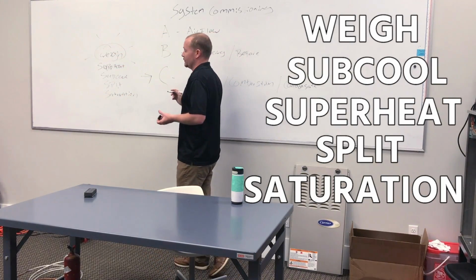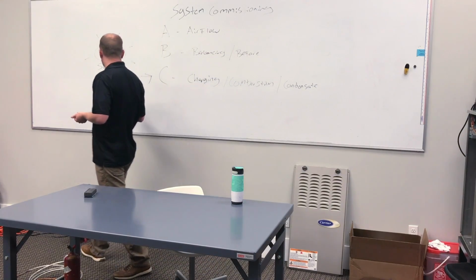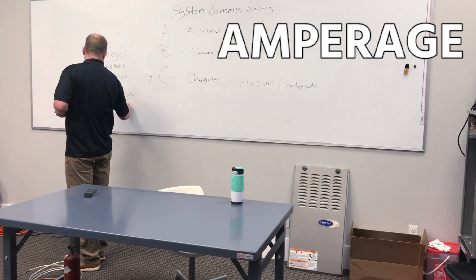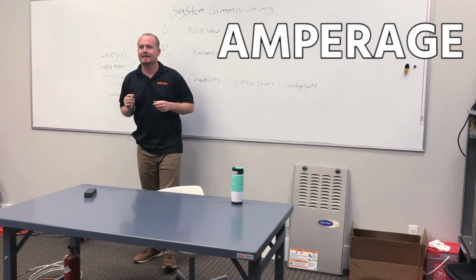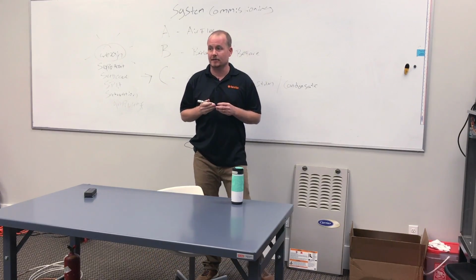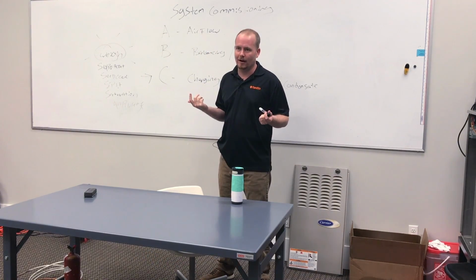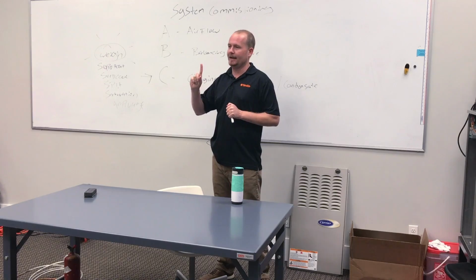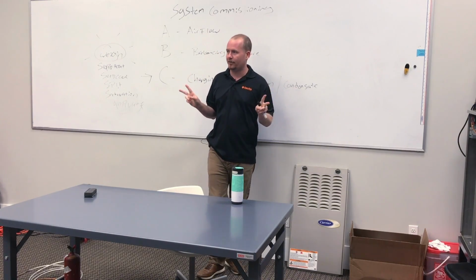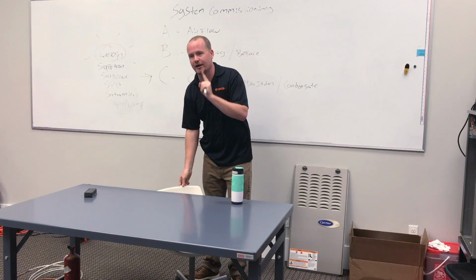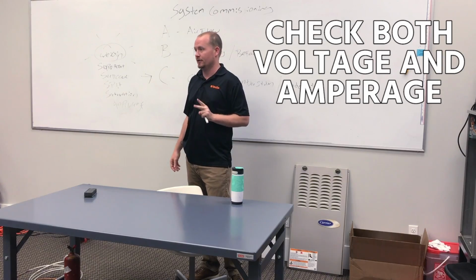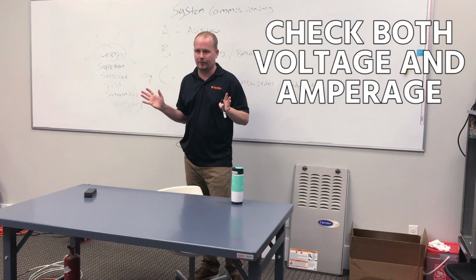We're going to throw in the electrical side. You're going to check amperage, right? On an install, it doesn't mean much. How many times have you stopped the process like, whoa, my amperage isn't right? Not very often. In fact, if I couldn't get you to do both electrical measurements, I would rather you check voltage than amperage of the two. You need to check both.